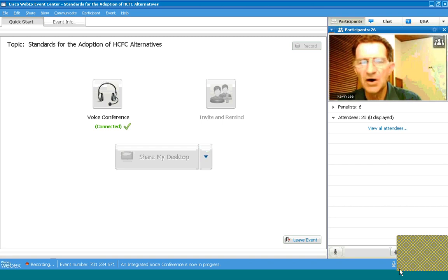And ammonia has been used as a refrigerant for a very long time, quite successfully. But even carbon dioxide, which is listed as a non-toxic refrigerant, if it leaks into a space where there's human habitation, it can be fatal above 5%. And that's not because of oxygen depletion. That's because carbon dioxide itself can sensitize the heart. You'll pass out and become unconscious, and if you're not removed from that area, you can die. And then, of course, the third big issue...